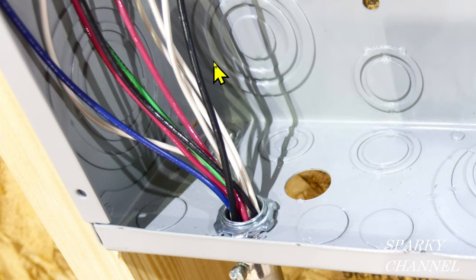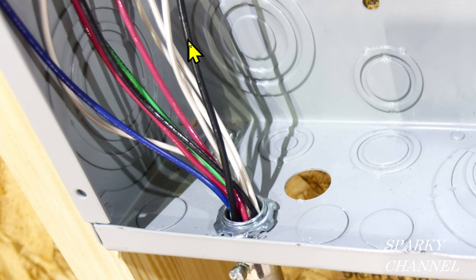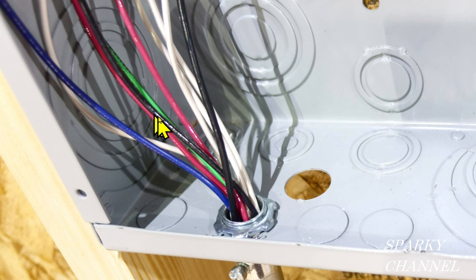Okay, this is a black wire and a red wire and another black wire and another red wire, and this is a blue wire. So that's five hot wires—we call them ungrounded conductors. One of them is 12 gauge and four of them are 14 gauge. So we have five hot wires.